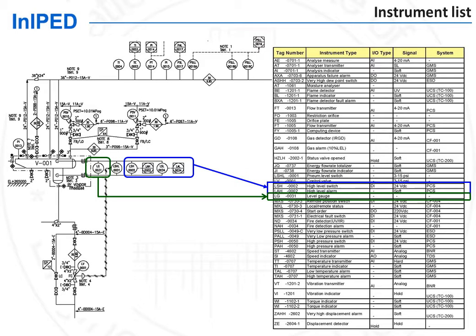The instrument engineer's first task is to produce the list of all instruments specified by process on the P&IDs. This forms the instruments list or instruments database, which is a central document for the instrumentation and automation discipline. It will list all the field instruments required to be specified, as well as all the list of IOs — input and output — for the systems, and will also give the capacity of these systems.